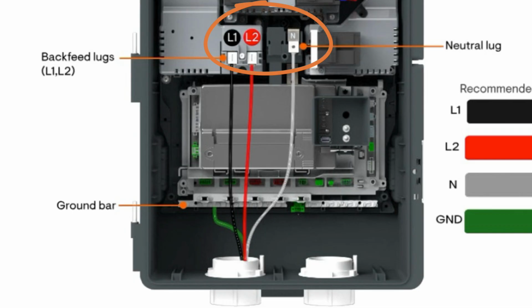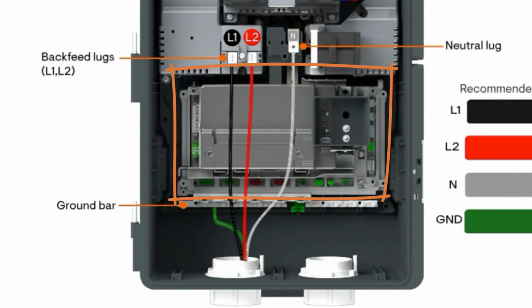These lugs can support 6 AWG to 2-aught wire. Next to the main combiner backfeed lugs are neutral lugs that can support larger gauge wiring when jurisdictions require the neutral be sized up according to the current carrying conductors. The lower part of the combiner contains the system IQ gateway. Behind the gateway is the combiner controller circuit board.